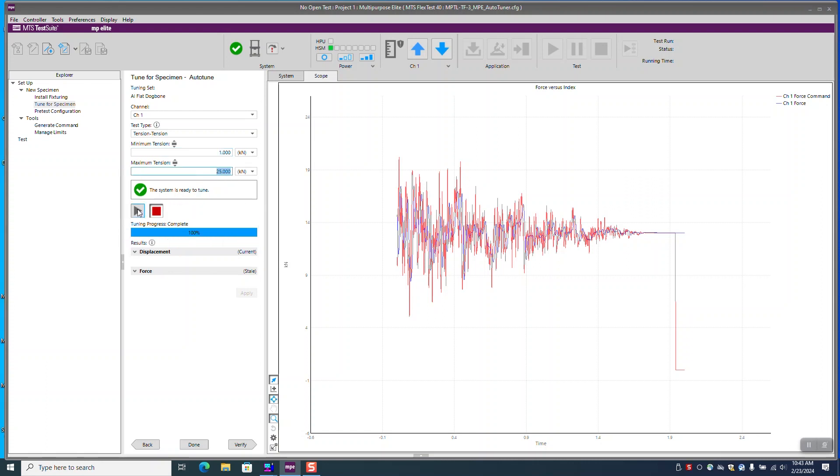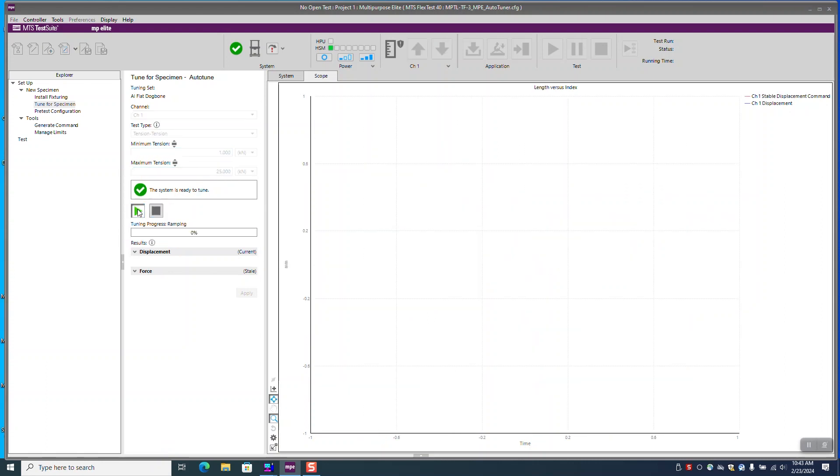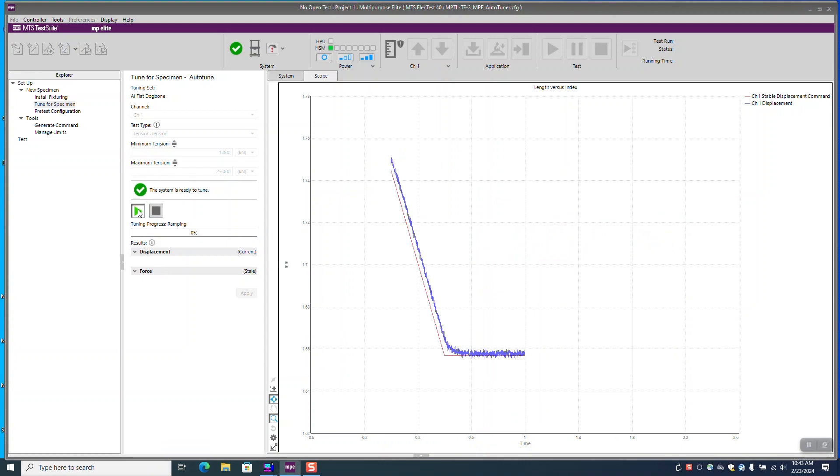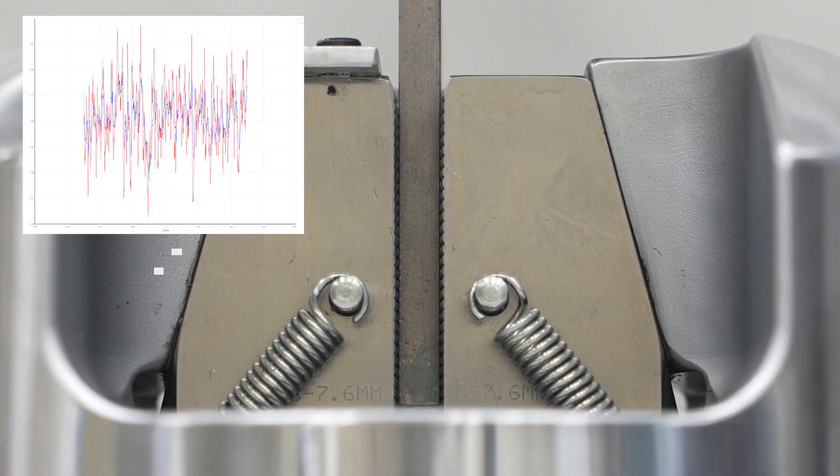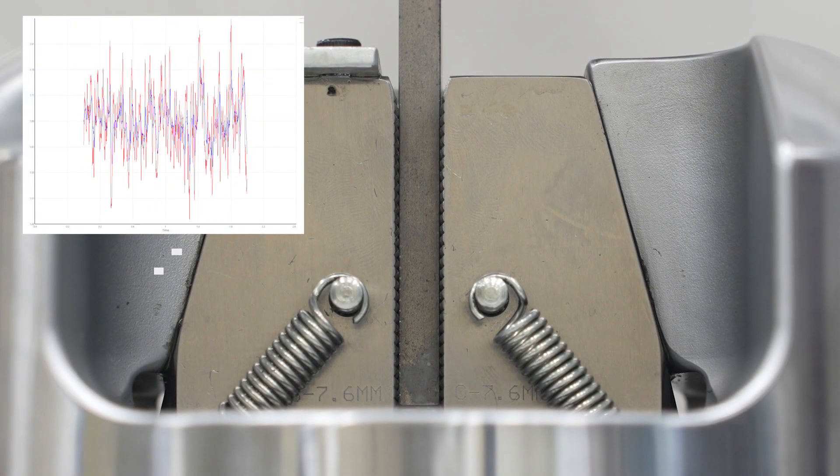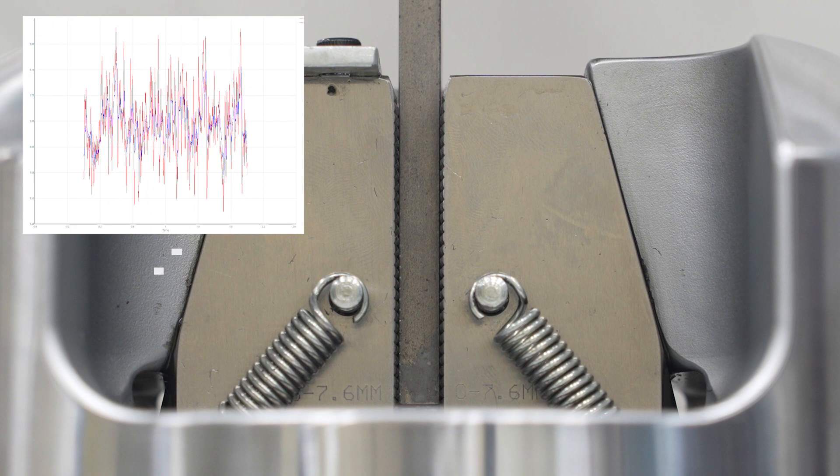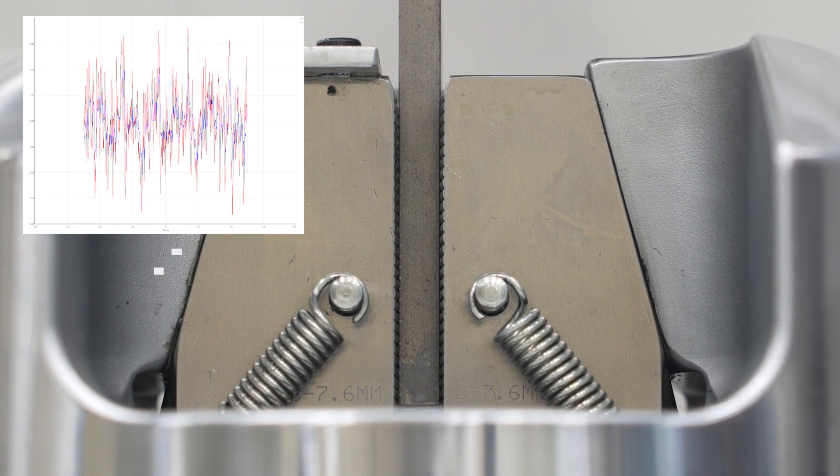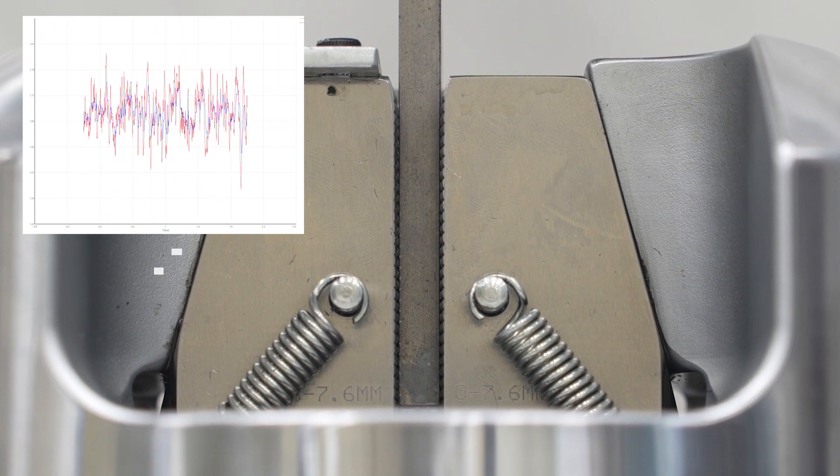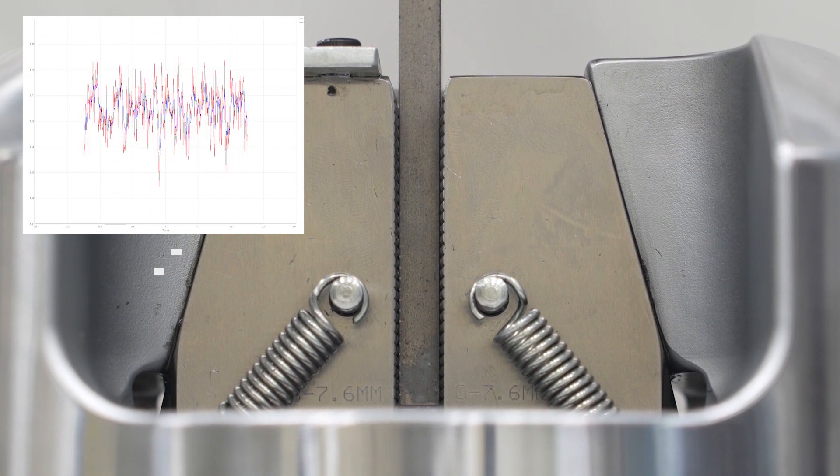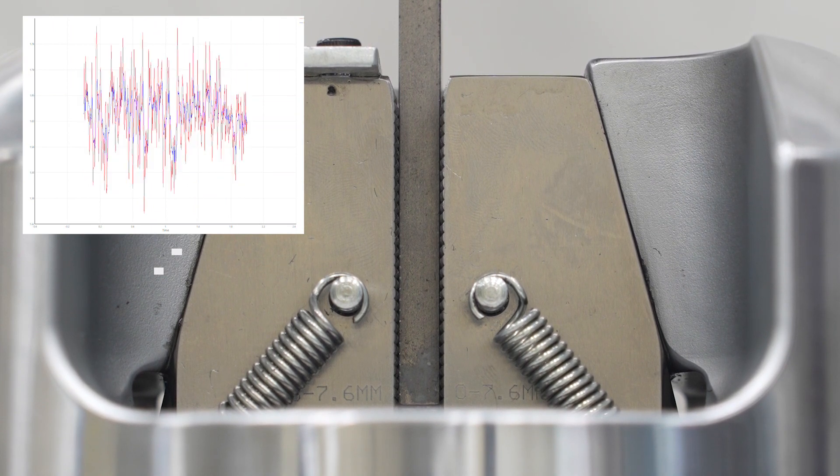The program will ramp to the mean of the force values and then cycle with a random noise pattern. The mean of the noise pattern may ramp up and down but will never cause the noise pattern to exceed the maximum forces in tension and compression.